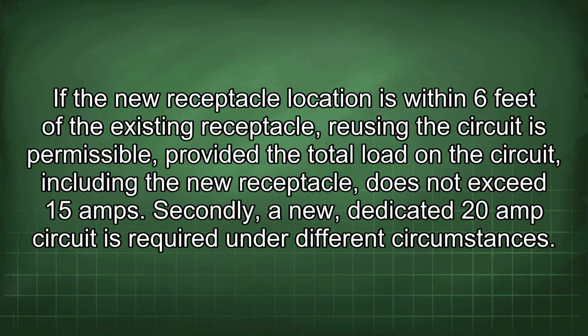If the new receptacle location is within 6 feet of the existing receptacle, reusing the circuit is permissible, provided the total load in the circuit, including the new receptacle, does not exceed 15 amps.